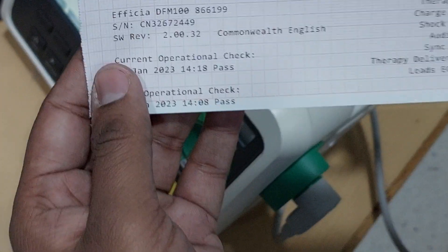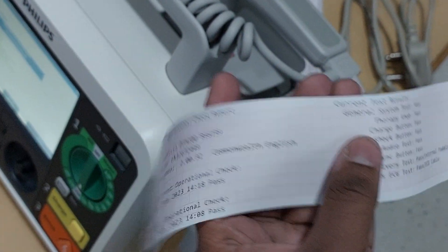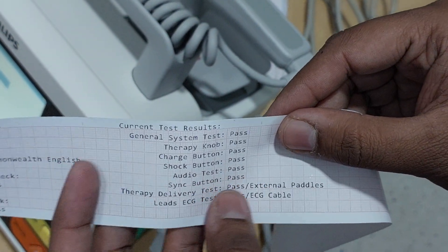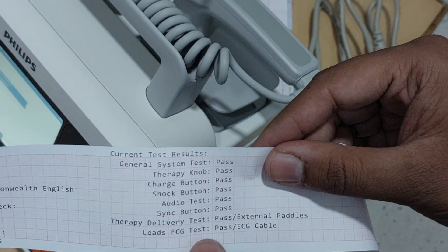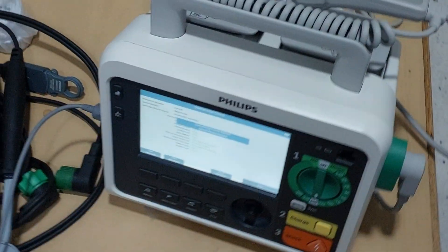You can observe the printout — this is the Efficia DFM100 serial number. Under General System Test: Pass. Therapy Knob: Pass. Charge Button: Pass. Shock Button: Pass. Audio Test: Pass. Synchronous Button: Pass. Therapy Delivery Test: Pass. External Paddles: Pass. Lead ECG Test: Pass. That means this machine is working fine and you can use it directly for the patient.